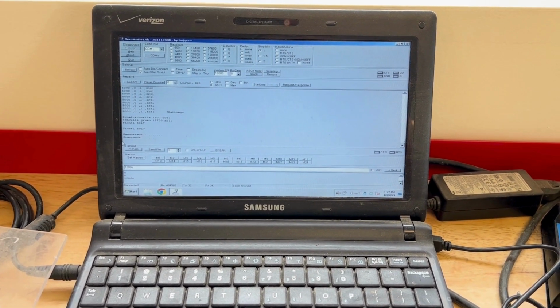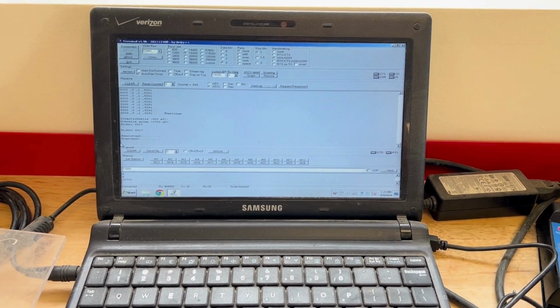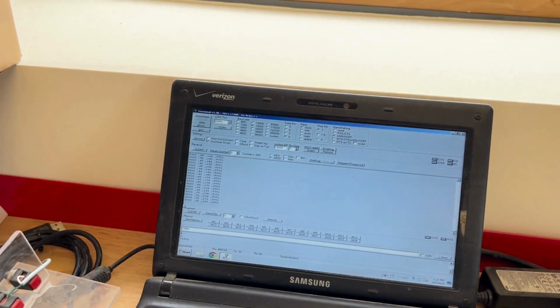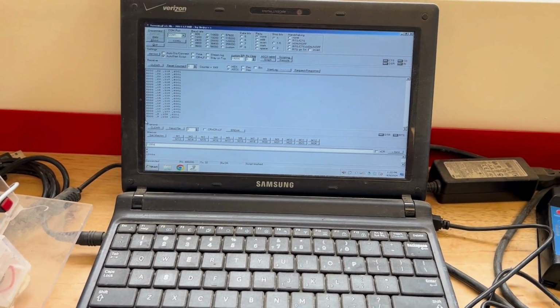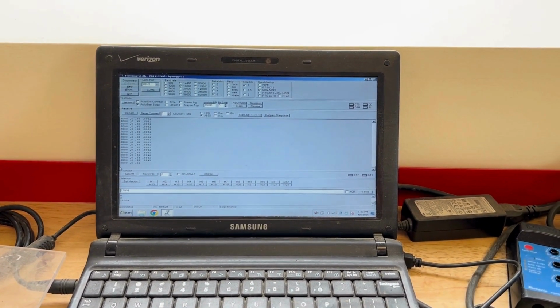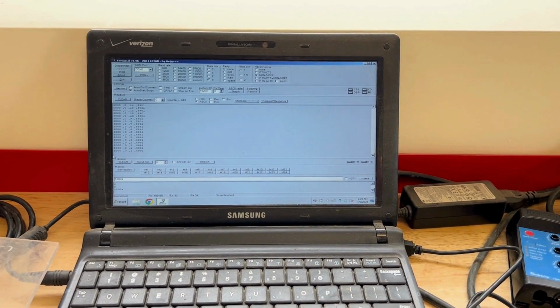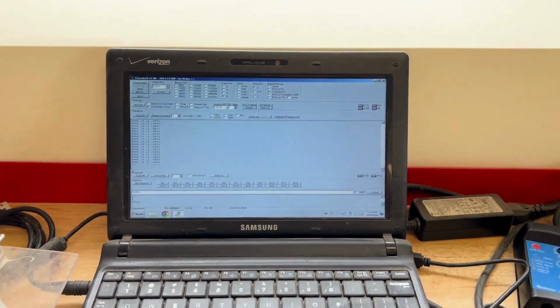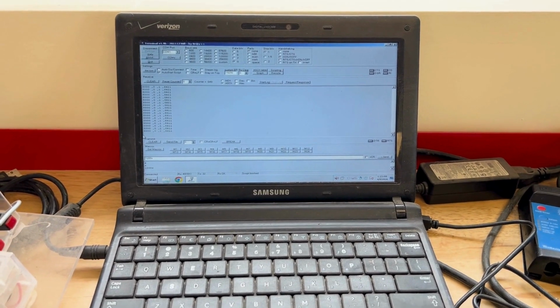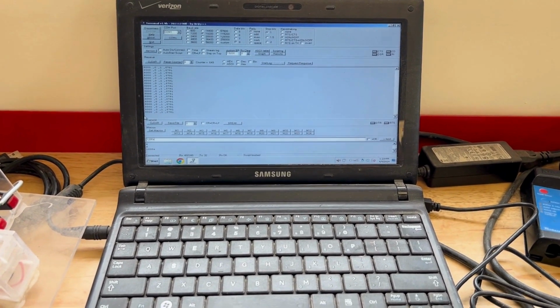So here I wanted to explain, in the past we always would have people send these in to have the optic sensor replaced. As I mentioned earlier in the video, now you can buy an optic sensor outright. That's part 5017.300. But as the website states, when you go to order spare parts, this should only be done on a unit made after 2021. And the reason for that is things were greatly standardized at that point. Now there's a great deal of consistency between optic sensors as well as circuit boards. And if it's older than that, you want to send it in.